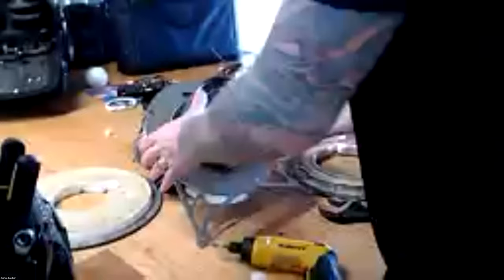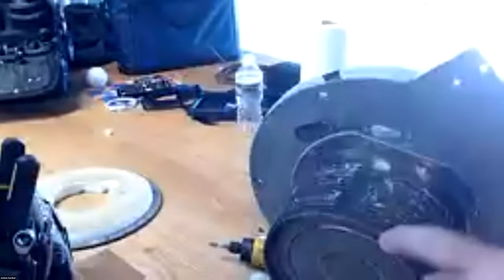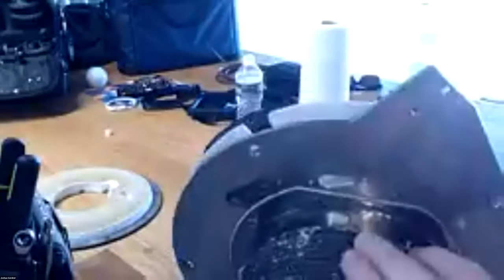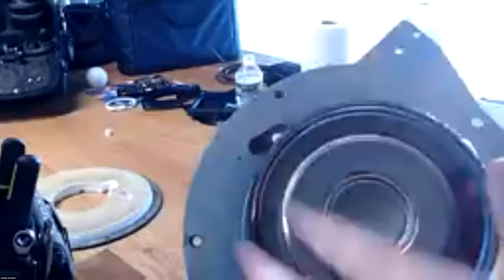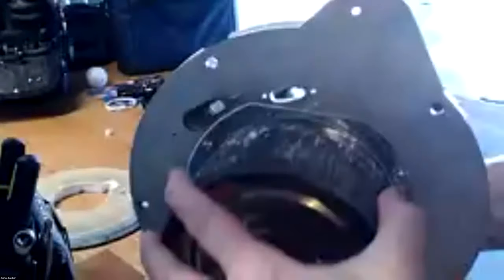So if you're doing a cleaning, let's say this insulation is really bad, we got to replace it. One little trick is this, you can kind of see it, where we pulled off that insulation, you get this white fuzz up here. And that can clog up that burner head, all right? That can prevent us from getting a good solid flame through there. So we want to keep this nice and clean. For the burner head too, we want to pop off the screws, pull this out, take a compressor and just lightly blow the inside out and clean everything out and try to spray all that gunk out. So we're going to reinstall the insulation.